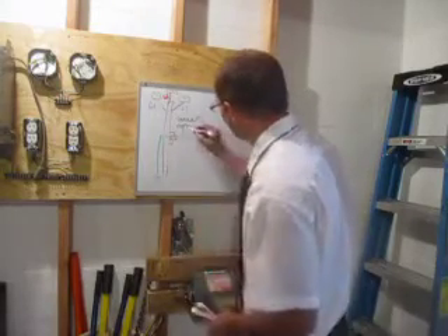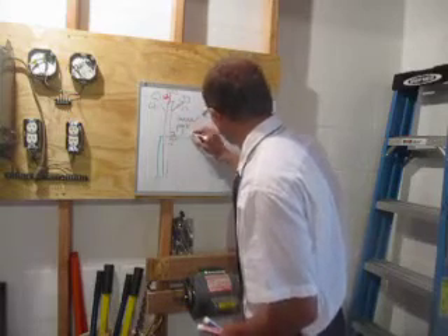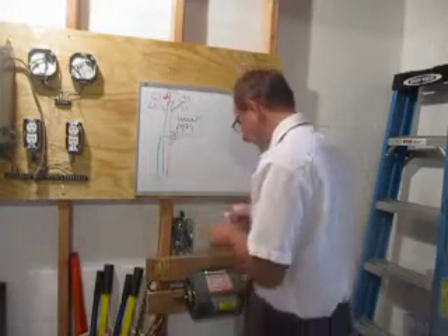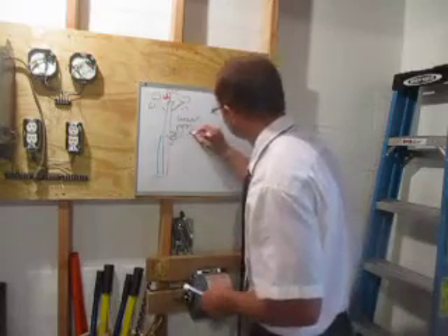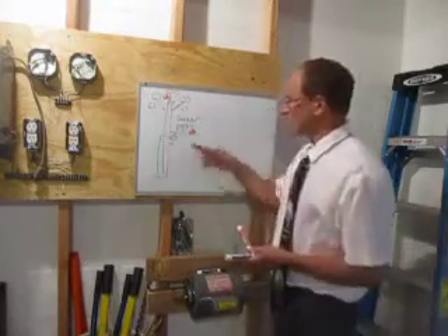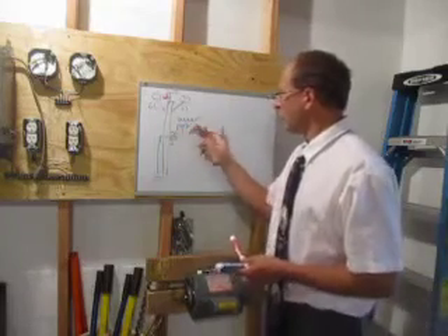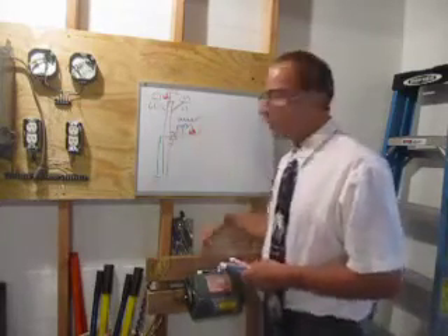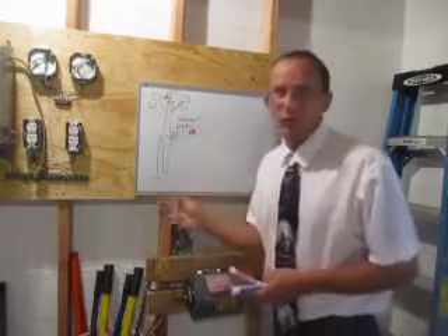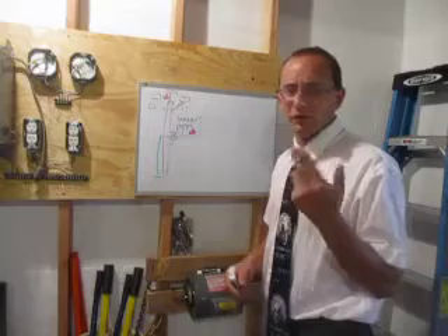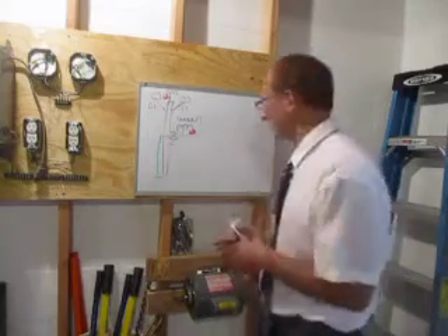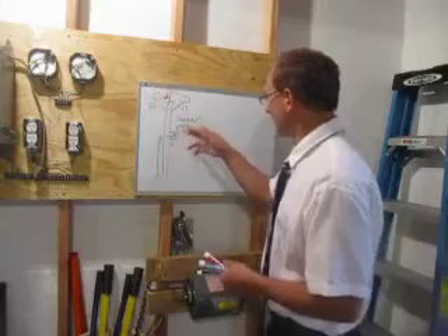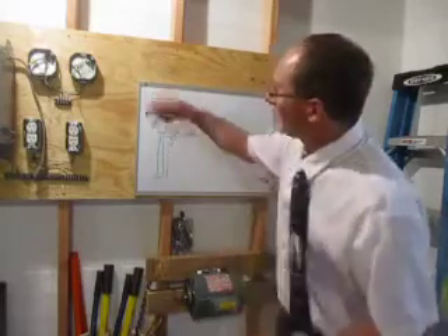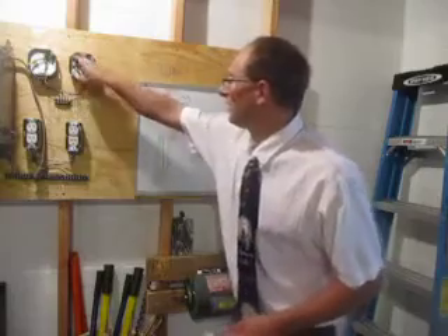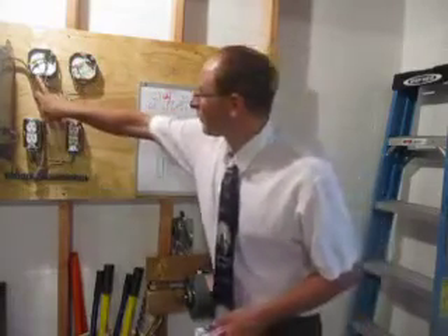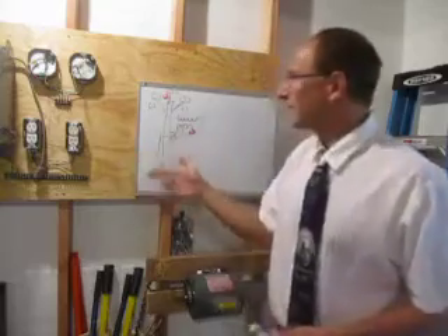And then in the single phase system 120/240, we have L1 and L2 here. Basically, this is 120 to neutral, 120 to neutral. L1 to neutral is 120, L2 to neutral is 120. But if you take your L1 to L2, you got 240 volts, for your stove, furnace, air conditioner, dryer, big appliances. But everything else is 120 to ground. Basically, this would be like one circuit. The L2 would be the red, and it would power half your house, and the black would power the other half of your house. You balance the load across that, that's how it works.